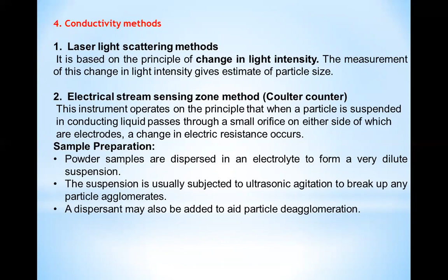The suspension should be sufficiently dilute so that particles pass through essentially one at a time. A constant voltage is applied across the electrodes to produce a current. As the particle passes through the orifice, it displaces its own volume of electrolyte, resulting in an increased resistance between the two electrodes.